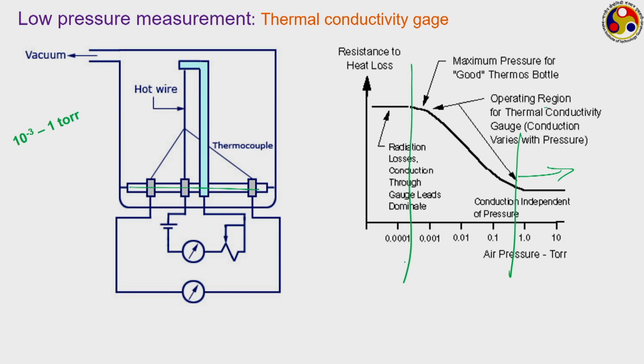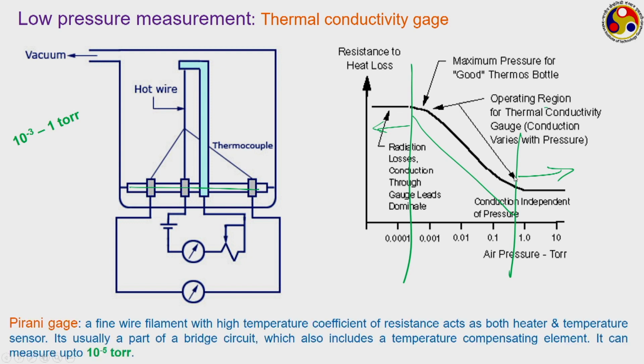Below this, radiation becomes significant in this zone, so the temperature is quite high and we can't get the measurement. But over this range, the thermal conductivity varies almost linearly with pressure, and accordingly we can use these gauges to measure pressure using this principle.